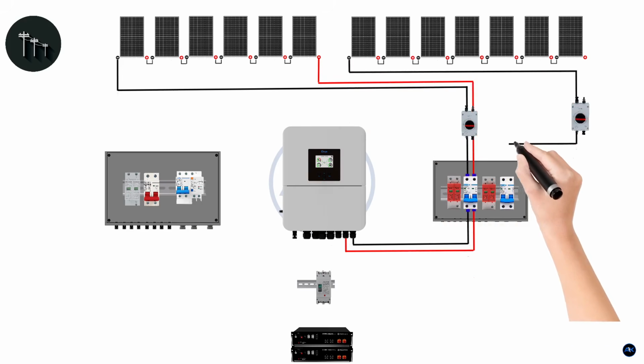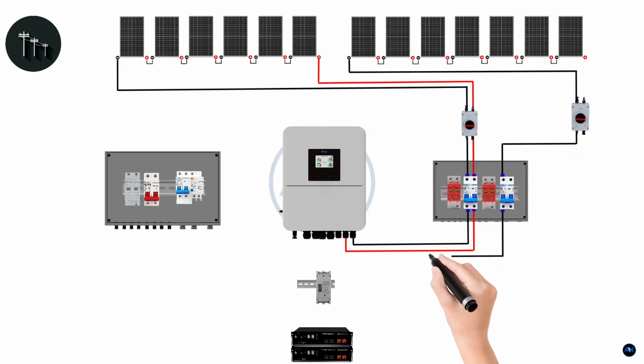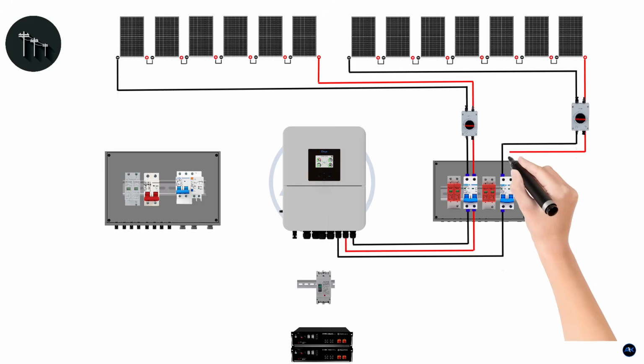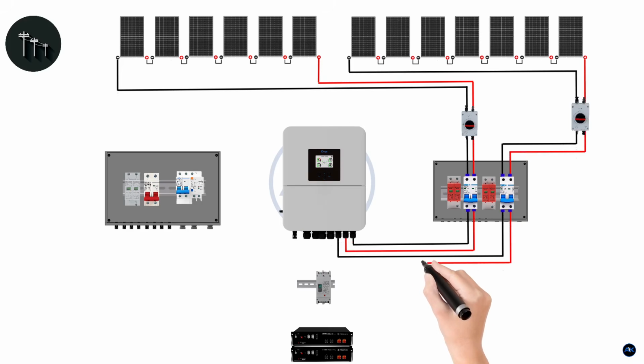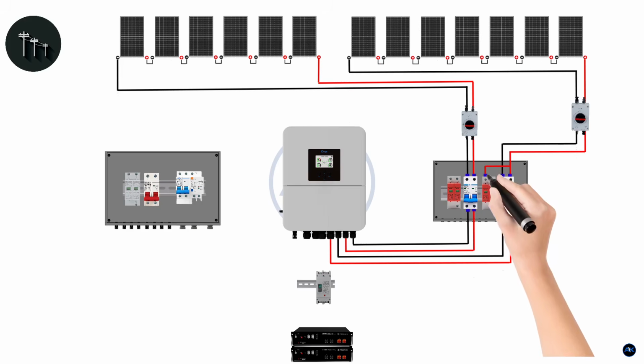Step 2. DC wiring, panels to DC-DB. Series connections: connect the positive terminal of one panel to the negative terminal of the next panel in your string. Parallel connections: once you have your series strings, connect the positive terminals of each string together and the negative terminals of each string together using appropriate branch connectors.